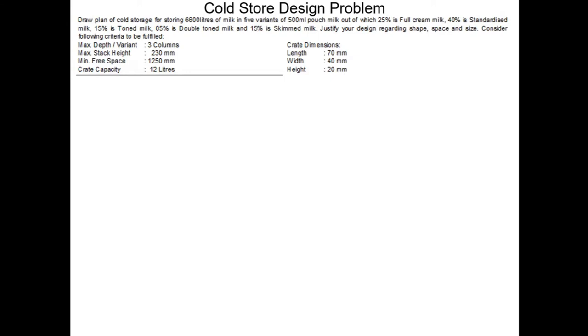Coming on to the last topic regarding cold store design. We already discussed one numerical problem regarding cold store - that was the potato one. This is another numerical problem regarding the designing of cold storage on the basis of what is required to be stored. The problem states: draw a plan of cold storage for storing 6600 liters of milk in 500 ml pouch variants.